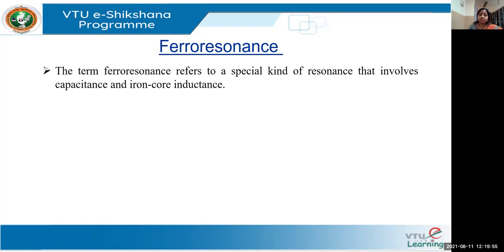When we talk about ferroresonance, we are all aware of what resonance is. But what do we mean by 'ferro'? Ferro is something which contains iron — here I'm talking about the transformer core. The key concept is that surge currents which strike the primary side of the transformer under no-load conditions cause the saturation level to be reached in the core of the transformer, which is a key point in understanding ferroresonance.